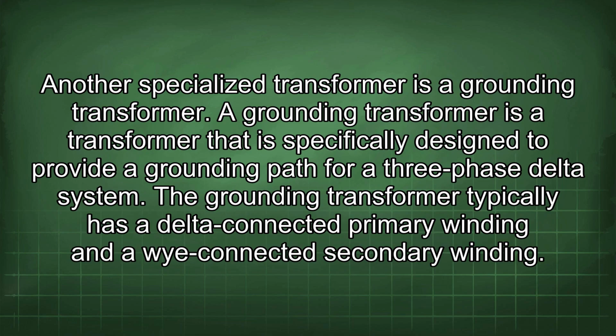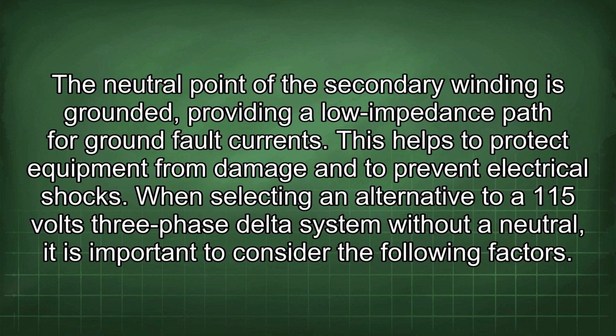Another specialized transformer is a grounding transformer. A grounding transformer is a transformer that is specifically designed to provide a grounding path for a three-phase delta system. The grounding transformer typically has a delta-connected primary winding and a Y-connected secondary winding. The neutral point of the secondary winding is grounded, providing a low impedance path for ground fault current. This helps to protect equipment from damage and to prevent electrical shocks.